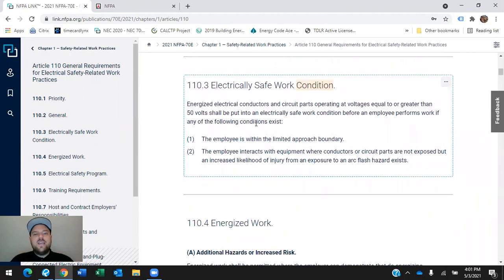110.3, electrically safe work condition. Energized electrical conductors and circuit parts operating at voltages equal to or greater than 50 volts shall be put into an electrically safe work condition before an employee performs work if any of the following conditions exist. Number 1, the employee is within the limited approach boundary. And number 2, the employee interacts with equipment where conductors or circuit parts are not exposed, but an increased likelihood of injury from an exposure to an arc flash hazard exists.